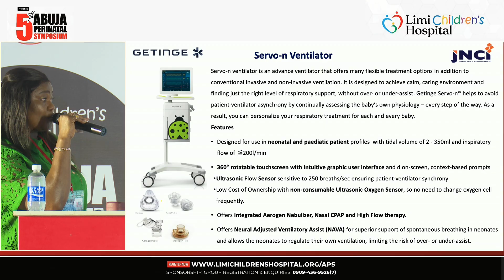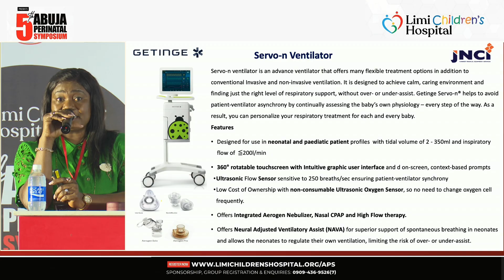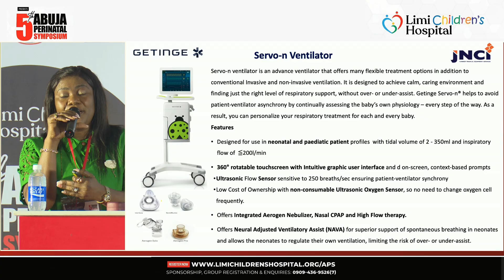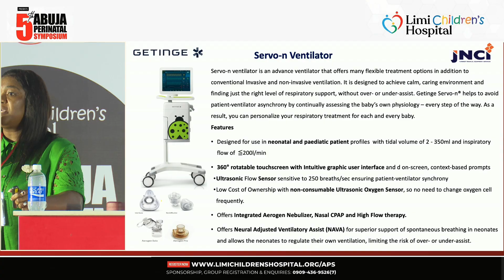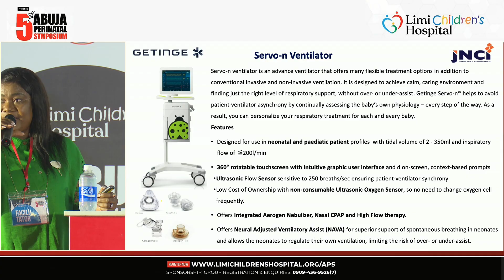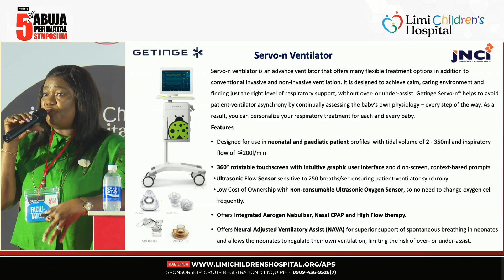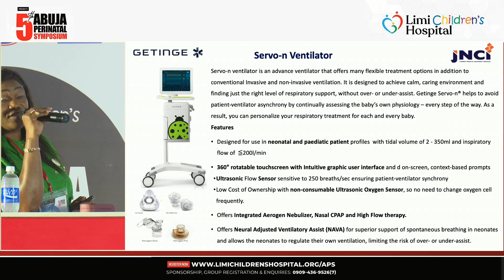It offers a technology we call neurally adjusted ventilatory assist, NAVA, which is an advanced monitoring module. It utilizes the signals that come from the diaphragm. So even before the baby makes an effort to take a breath, the ventilator actually has that inkling that the baby is about to take a breath. And because of this, the ventilator can either step down for the baby to take the breath, or take over and deliver a breath in a situation where the baby fails or a breath is not initiated.